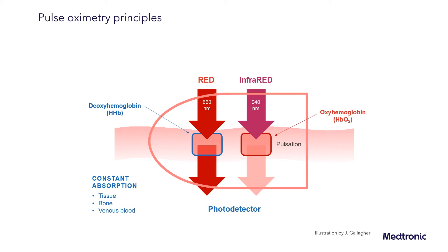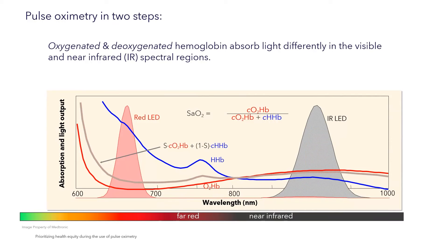We can see in more detail here how oxygenated and deoxygenated hemoglobin absorb light differently in the visible and near-infrared spectral regions. On the left of the diagram is the spectrum of red LED light, and we can see that that light is preferentially absorbed by deoxygenated hemoglobin, represented by the blue line. On the right side, we see the infrared LED spectrum, which is preferentially absorbed by oxygenated hemoglobin, represented by the red line.